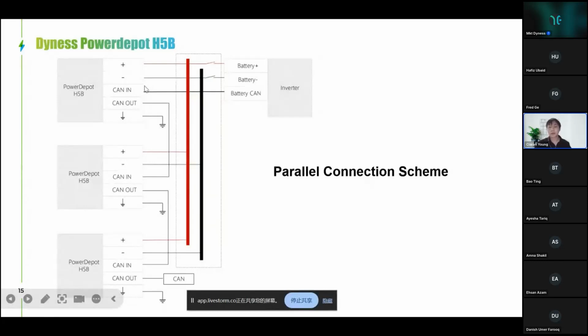For the communication part, you connect the CAN-in port of the master battery with the combiner box together with the inverter battery. Here, the communication port, and its CAN-out, will be connected to any other slave battery - CAN-out to slave battery CAN-in.